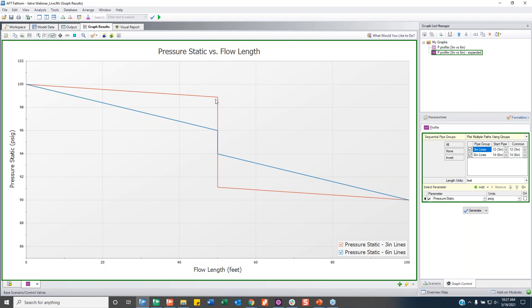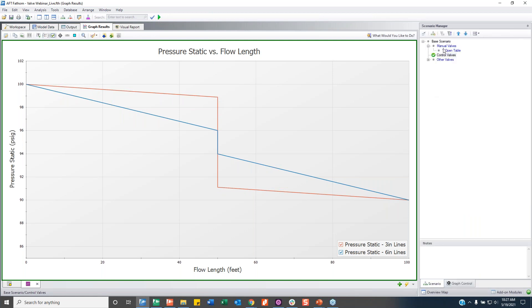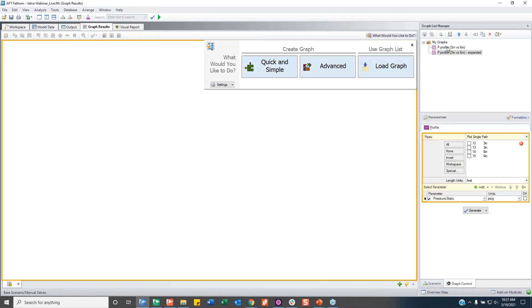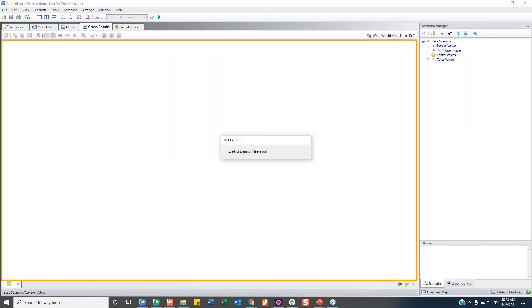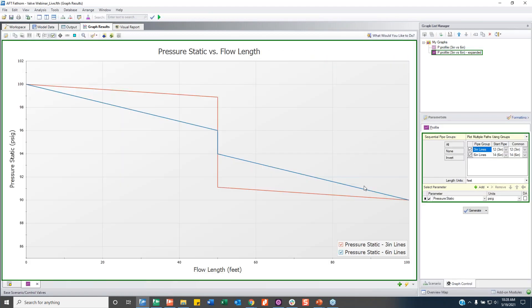Looking at the pressure graphs, the two control valve scenarios show very different pressure drops. The manual valves from before had the same pressure drop because they had the same Cv. The control valves here have a much larger pressure drop across the valve, so flow is not moving as fast — you see a shallower-sloped pressure profile along the pipe.